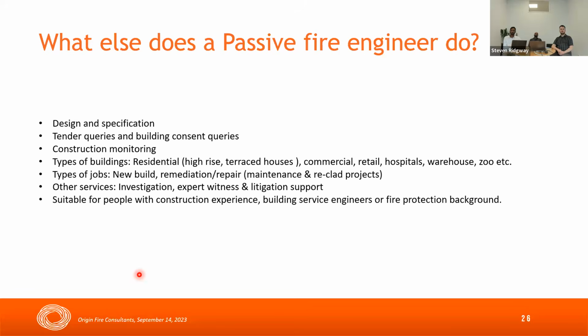So we provide that. A major part of my job role involves construction monitoring. That's when the building is actually being built. We visit site at different intervals and make sure all the fire stops are being installed correctly as per the spec. We make sure that the contractor knows what they're doing, and that they're installing the right product to the right service, as the manufacturer has specified or instructed. Because if you deviate from the manufacturer's instructions, then you have to go back to the manufacturer to ask their advice on whether the system will work or not. So we make sure that the contractor understands this and sticks to the instructions.